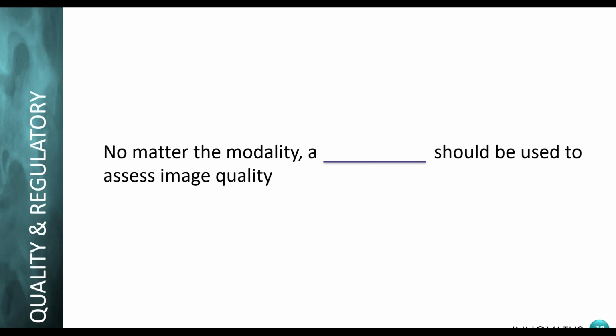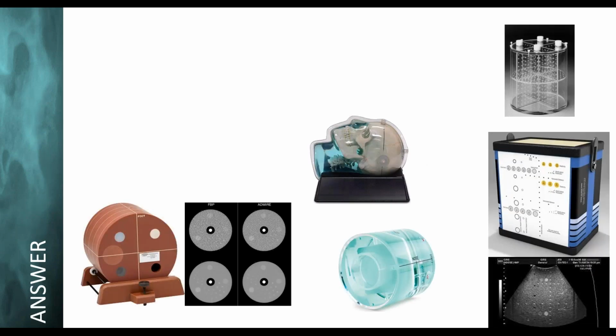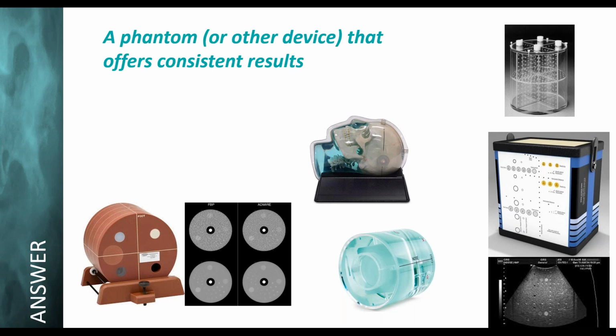There are phantoms available for all imaging modalities. The good thing about a phantom is it's objective. As I mentioned, I did service for 25 years. I've done clinical applications. My phantom is my body. Every time I get in front of a machine, first thing I do is my shirt comes up, put some gel on the probe, I pop the probe. I know my body better than anybody. I know exactly what I look like.